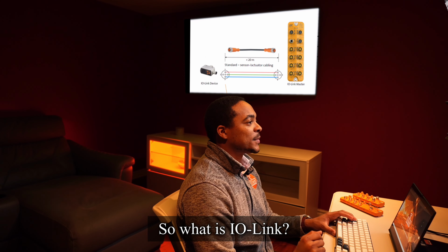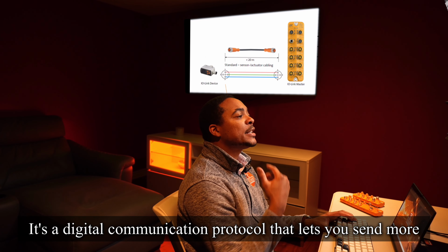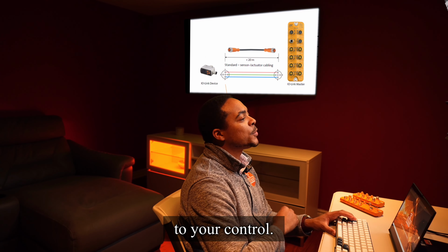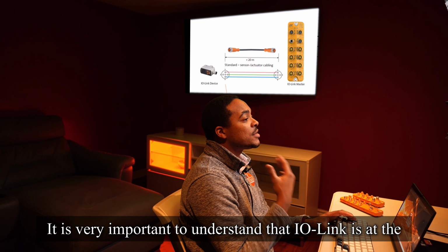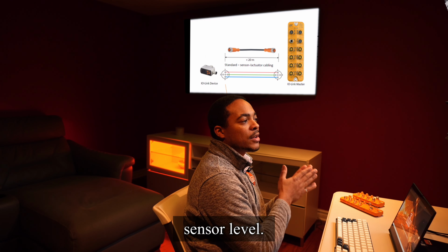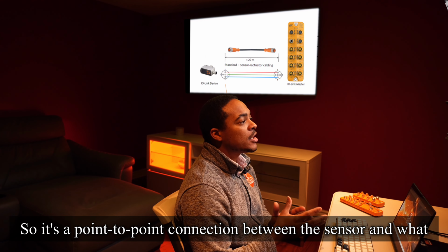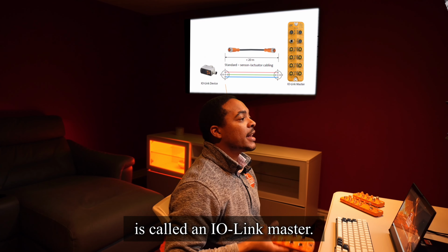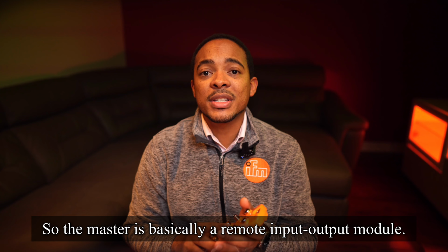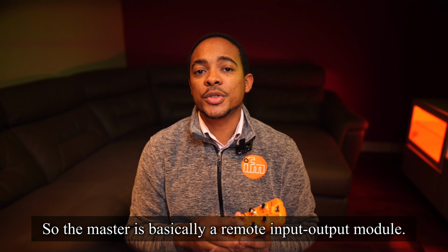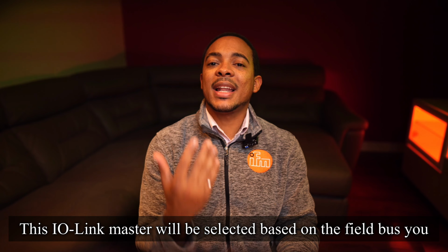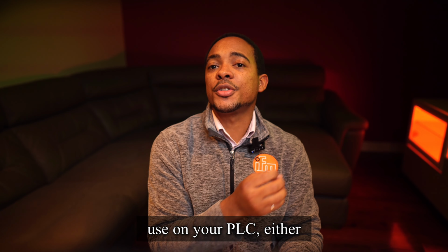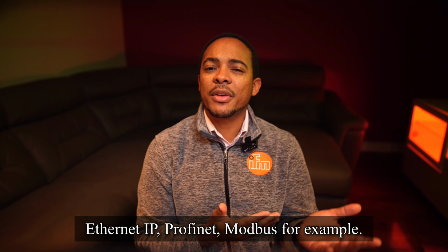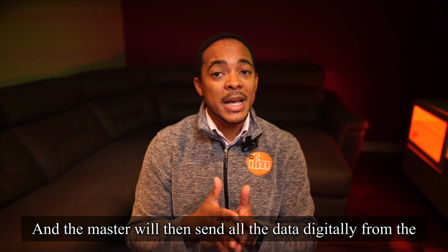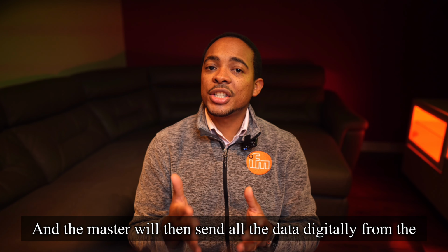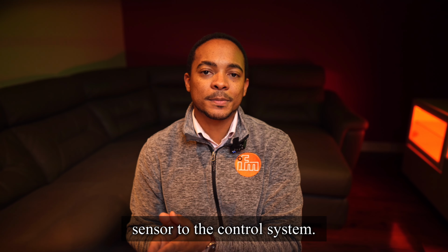So, what is IO-Link? It's a digital communication protocol that lets you send more information from your sensor to your control. It is very important to understand that IO-Link is at the sensor level. So it's a point-to-point connection between the sensor and what is called an IO-Link master. So the master is basically a remote input-output module. This IO-Link master will be selected based on the fieldbus you use on your PLC, either Ethernet/IP, Profinet, Modbus, for example. And the master will then send all the data digitally from the sensor to the control system.